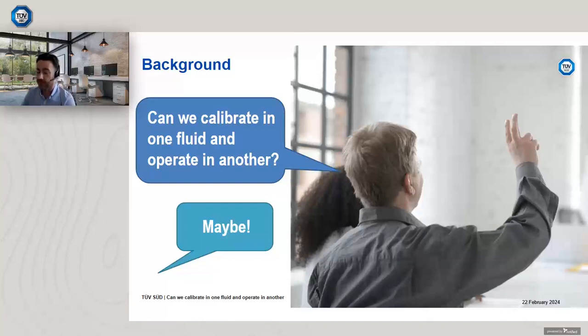It's partly because there are so many variables, so many parameters that need to be known first to say whether you can calibrate in one fluid and operate in another. In actual fact, if I was being semantic, I would say that if you ever send your flow meter to a calibration laboratory to be calibrated, then you're already calibrating in one fluid and operating in another, because no two fluids are going to be identical, even if it's natural gas or oil.